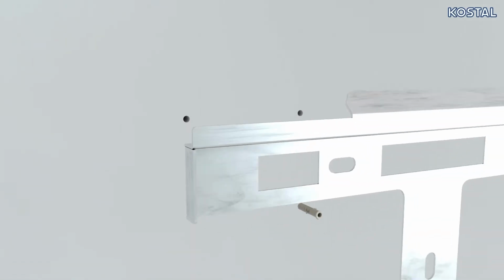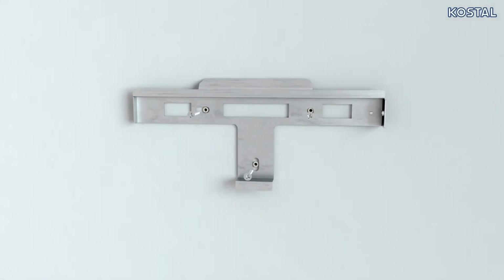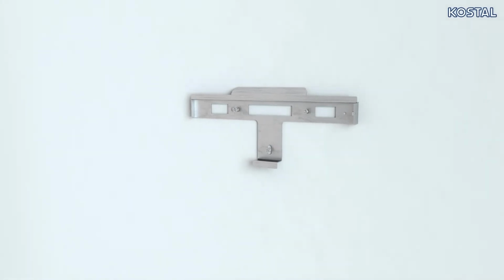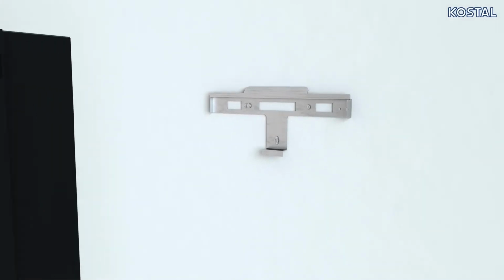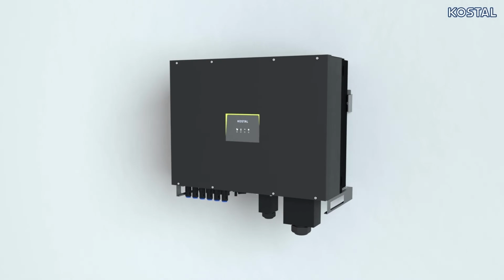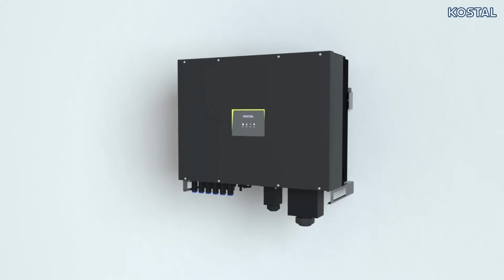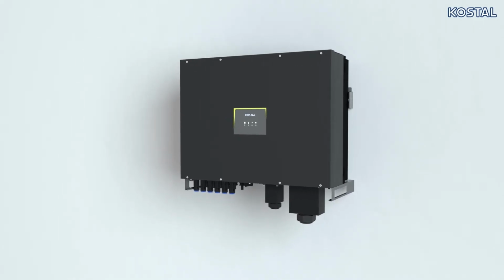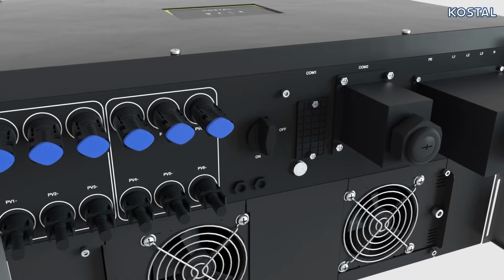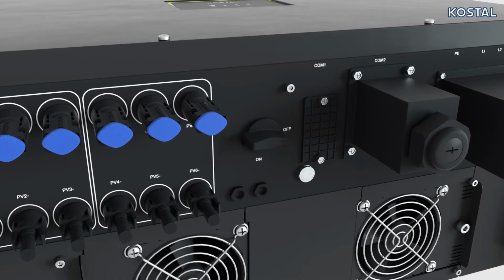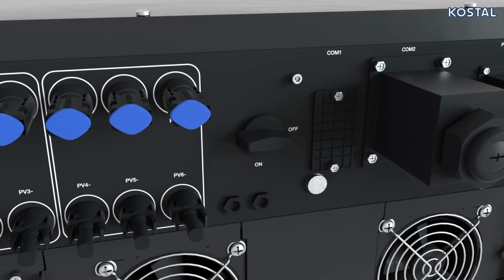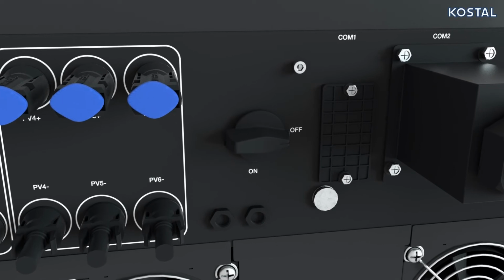Fit the assembly bracket vertically on a level installation surface. Hang the PIKO CI 30 centrally on the assembly bracket, and also use the lock screw provided to secure the inverter in place. Ensure that the DC switch is in the off position, and that the AC line is voltage free and secured to prevent it being switched back on.